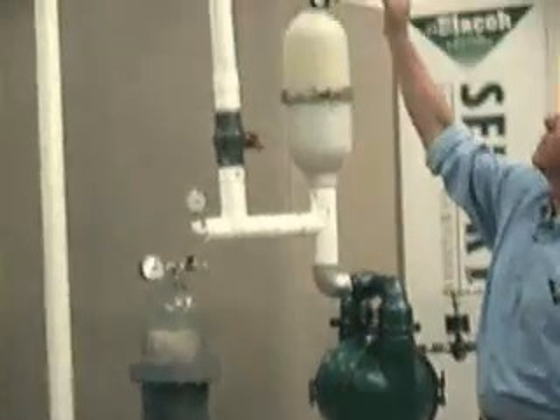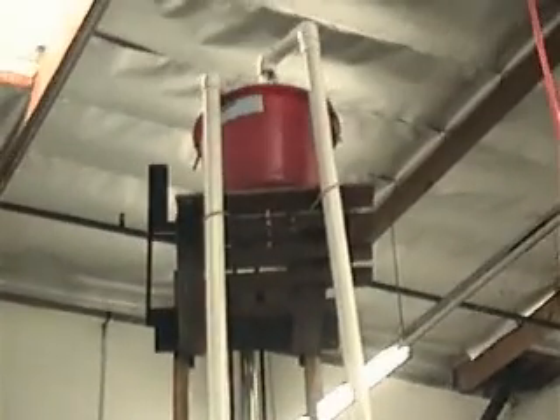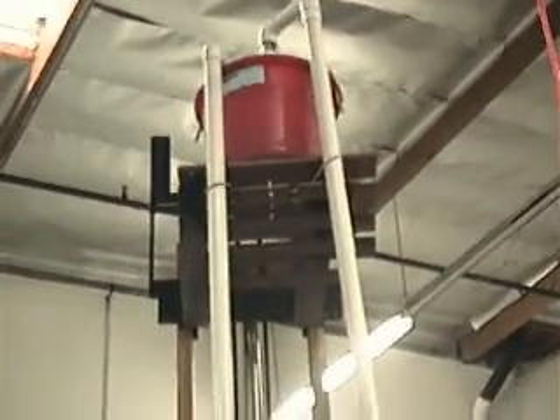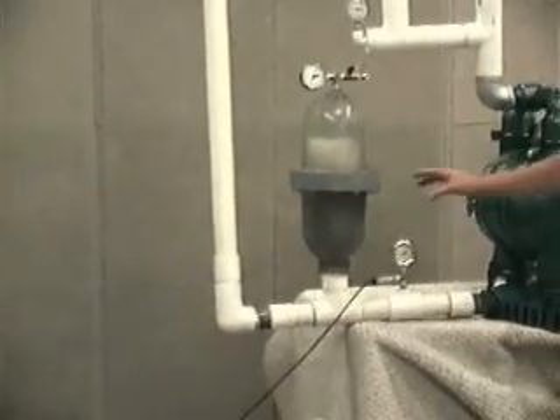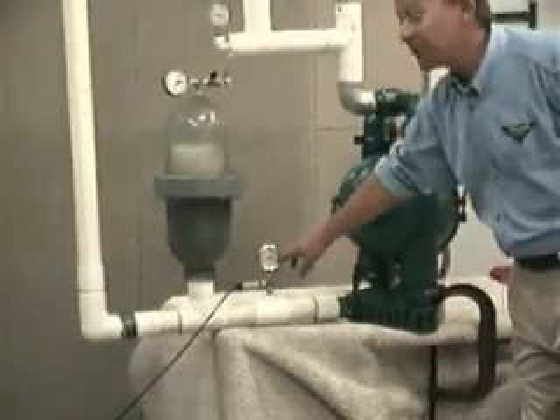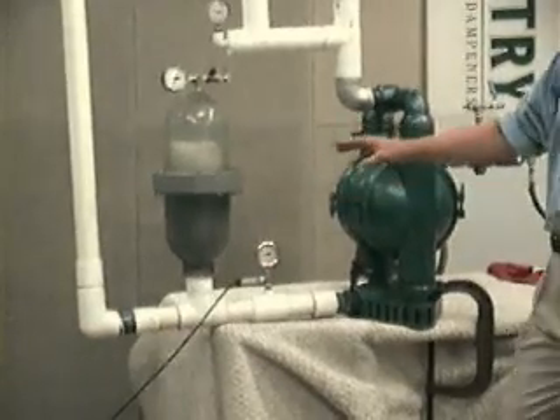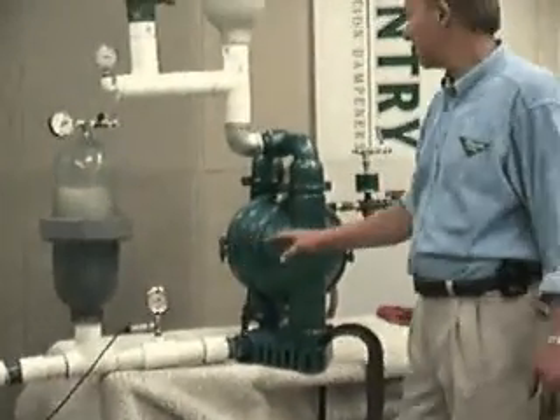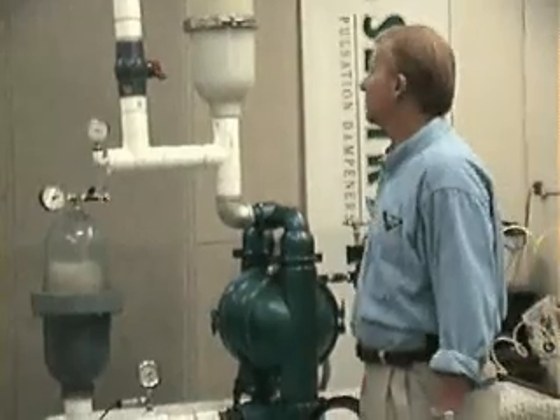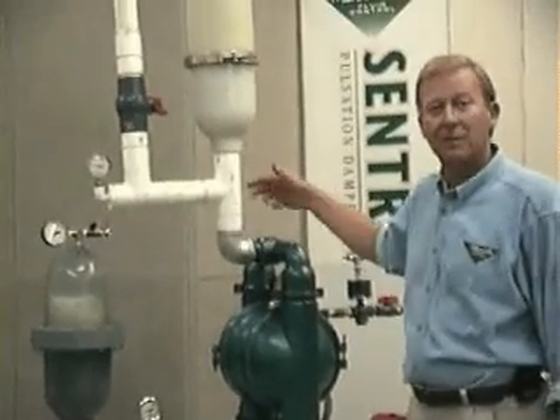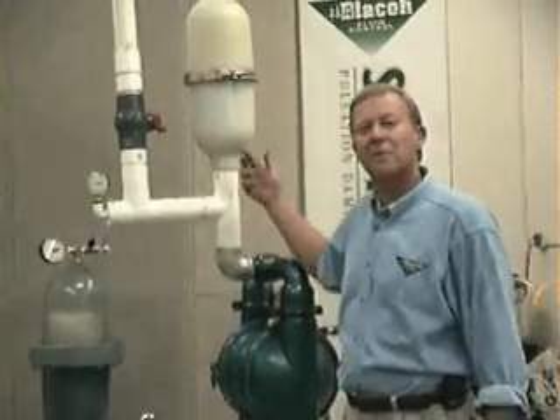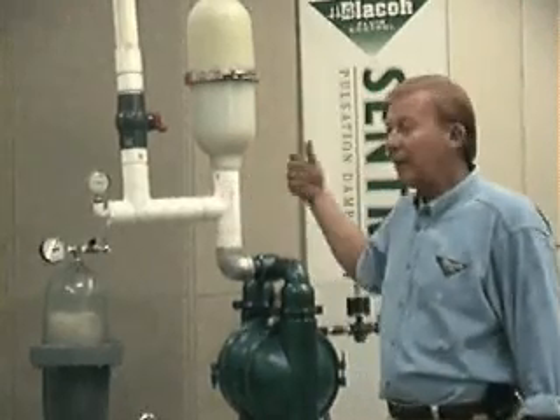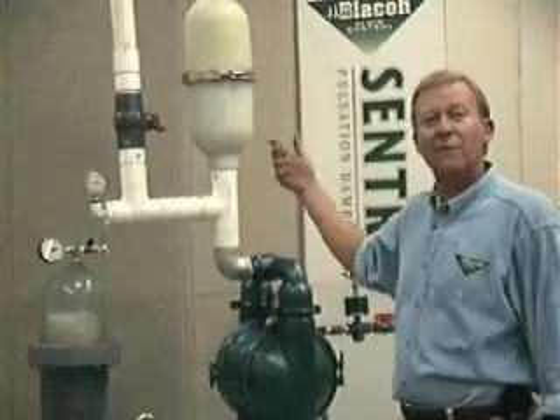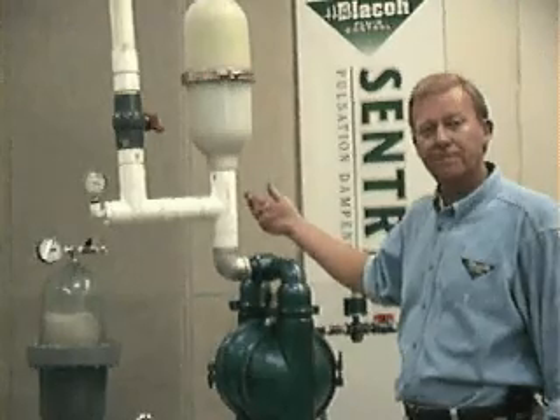Also observe that the inlet pipe is now vibration free and protected from damage to joints, threads, gaskets, gauges, and other components on the inlet side of the pump. We have, in effect, turned a reciprocating positive displacement pump into a centrifugal pump from a flow and pressure point of view.